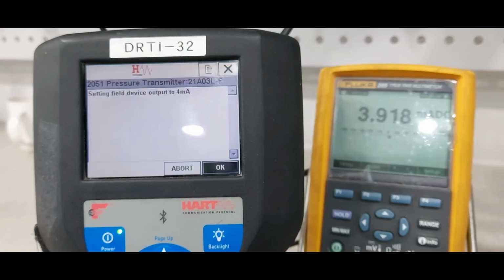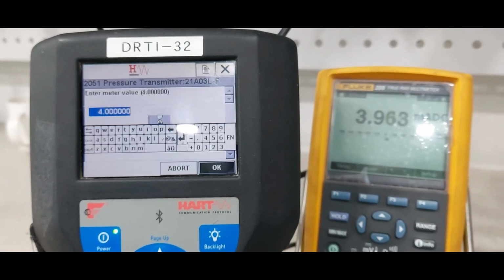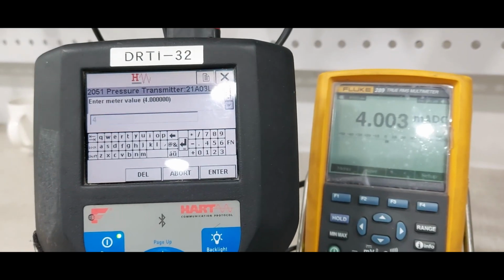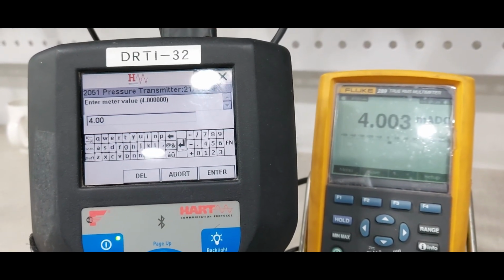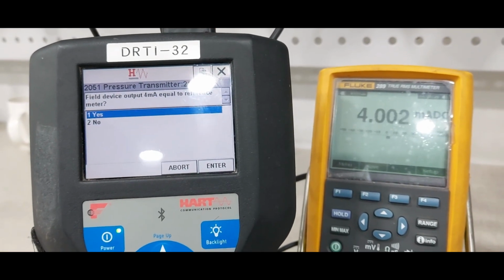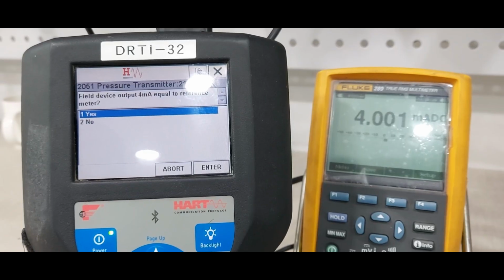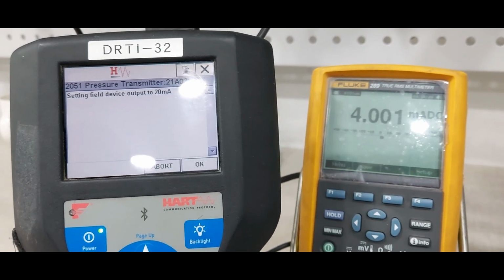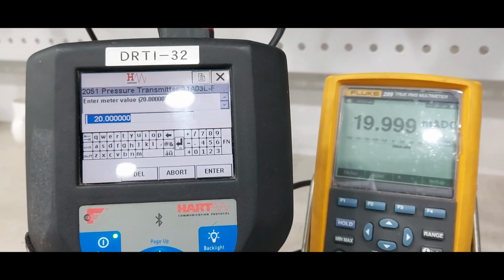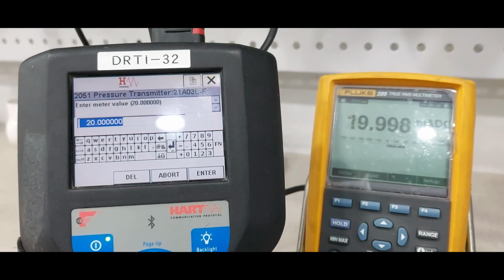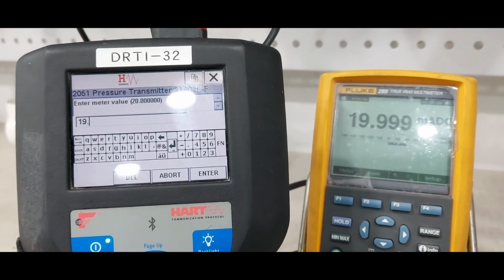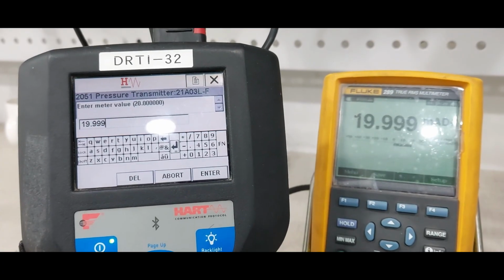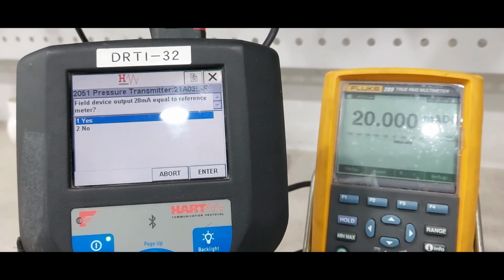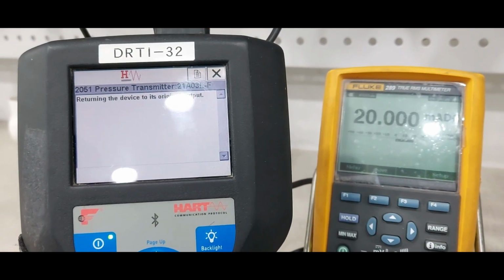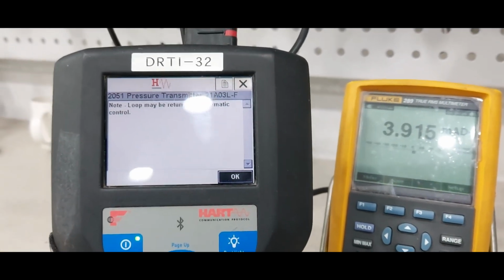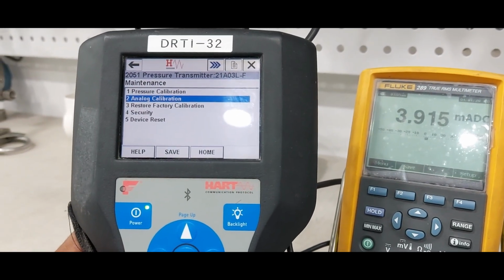Select the field device output to 4 milliamps. Okay. Enter the output value, 4.003. Both are equal. Select it, OK. Then 19.999, enter, then enter and OK. Now analog calibration is completed.